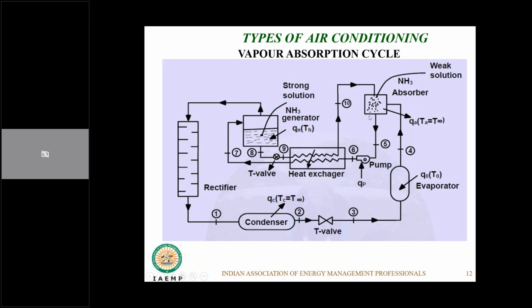In the absorber, we want the temperature as low as possible, close to ambient, so that it can absorb the maximum amount of ammonia in water. As it goes through the absorber, it comes through the exchanger. We want to raise its temperature so that it can come to the generator at the highest temperature possible. In the generator, the temperature is enhanced further until it reaches a saturation temperature, where the ammonia is released from the strong solution of ammonia and water. It then passes through the rectifier, where any water vapor is removed, and it comes into the condenser.